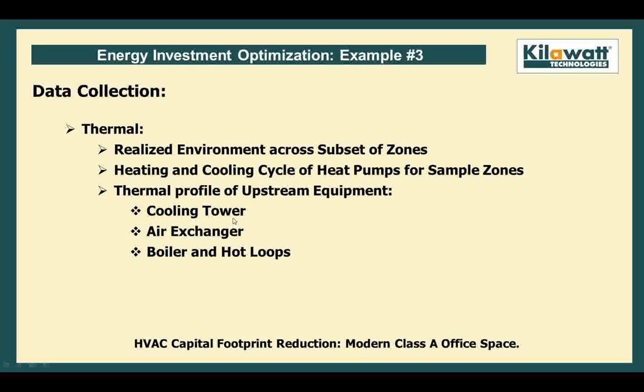A lot of people that we have run across only look, in this case, at the heat pumps themselves. While heat pumps do consume a tremendous amount of energy by their operation, the majority of energy in a building is actually by the larger upstream units that most people ignore. One, because they're somewhat difficult to get to. The air exchanger was on top of the roof. It's kind of windy up there. The cooling towers are either on top of the roof or in inaccessible areas. And in this case, the boiler room, well, the boiler room was just very hot.